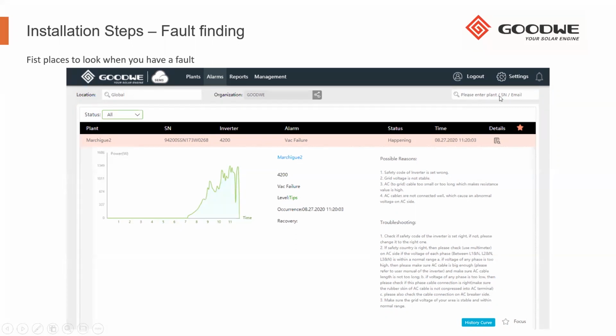You type in the plant name or serial number. You'll normally have to type it in here, wait a little while, and then it'll pop up, and then you can click it to filter it to that plant. You'll see it then lists the plants for us, the alarm which it is giving, as well as the status. So you'll see this one is a VAC failure, status is happening. You can also click on the details. This will give you a bit of detail regarding the failure and the possible reasons for the failure, as well as troubleshooting.